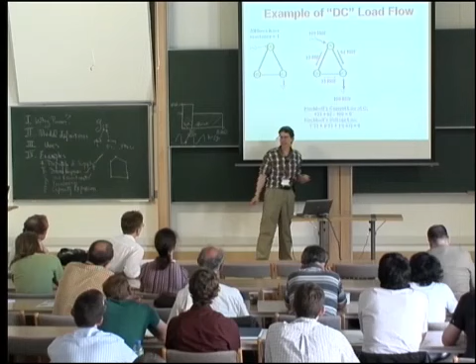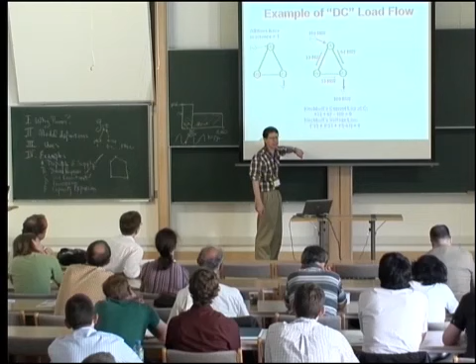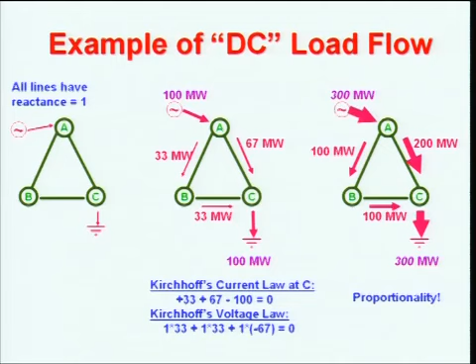If you write down the current law, these are analogous to Kirchhoff's current laws: at every point, flow in has to equal flow out. For example, at C, 33 plus 67 minus 100 equals 0. The analogy to the voltage law is that if you go around from A, B, and C, the power flow times the reactance has to add up to 0 by the time you get back to the start. You actually have four of these equations, of which three are linearly independent, and you can solve for the three flows, giving that result. Because these equations are linear, if you triple the inputs, you get triple the outputs.